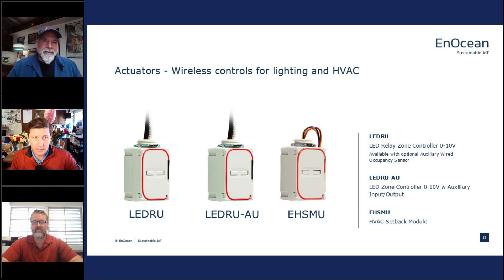The device in the middle, our LEDRU AU—AU stands for auxiliary input and output—gives you the capability of controlling fixtures while also interfacing with a third-party system, whether it's overriding lights on or off, or providing occupancy status via a low voltage contact closure, which is common in HVAC systems here in the US. We can use the LEDRU auxiliary output to give that indication to an HVAC system with a low voltage dry contact, or use our HVAC setback module, built specifically for those interfaces, which takes a 12 to 24 volt input that many VAV boxes and HVAC systems provide, giving a simple interface for temperature and occupancy control.